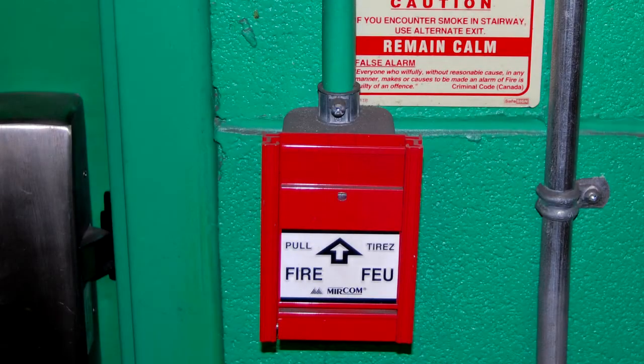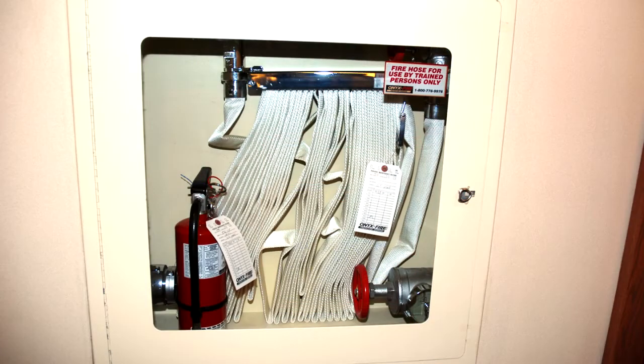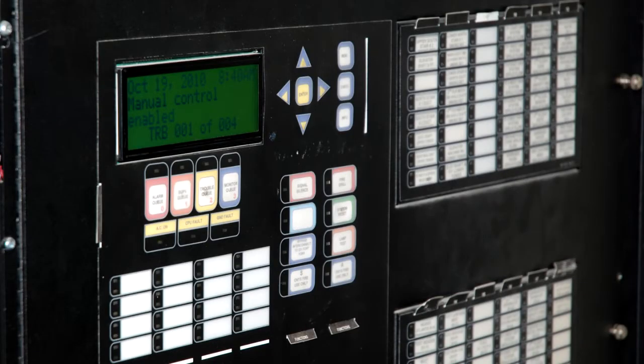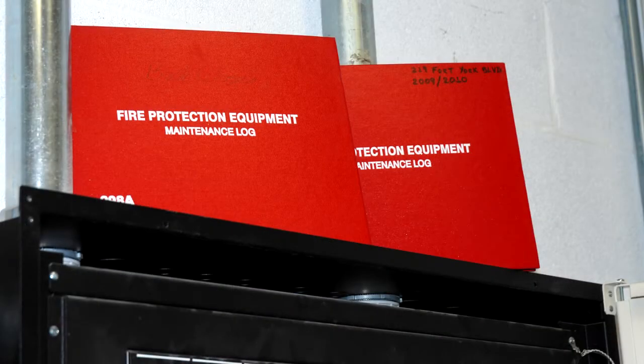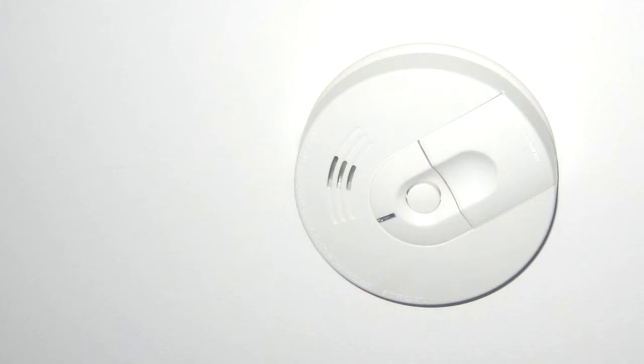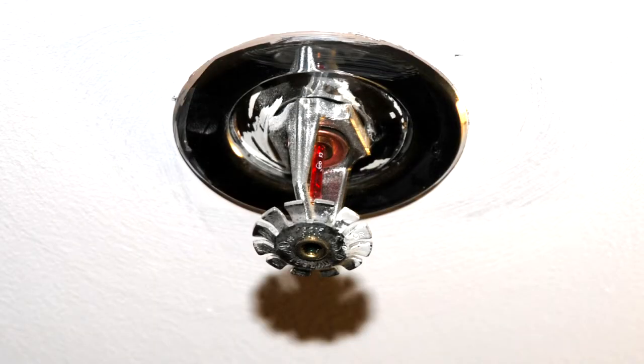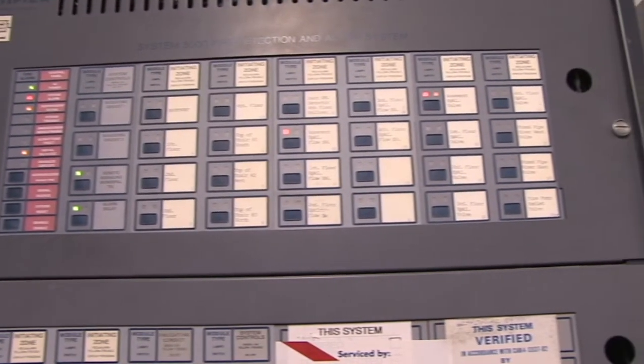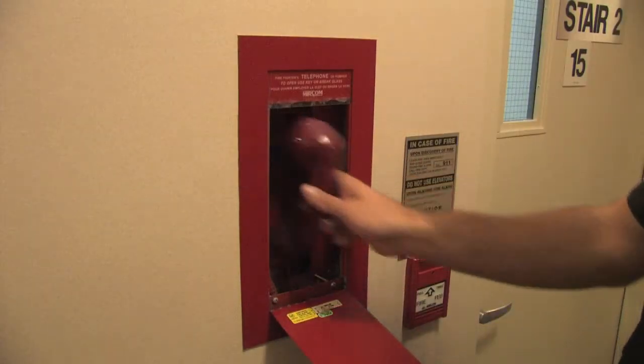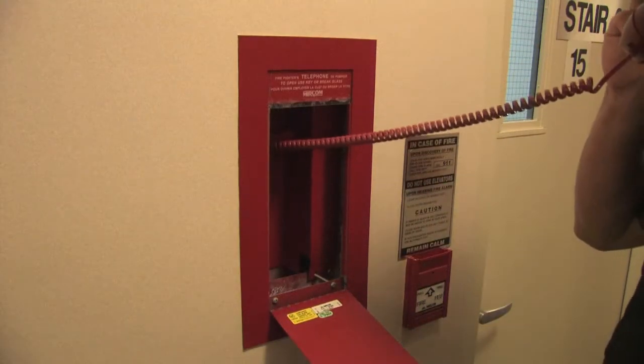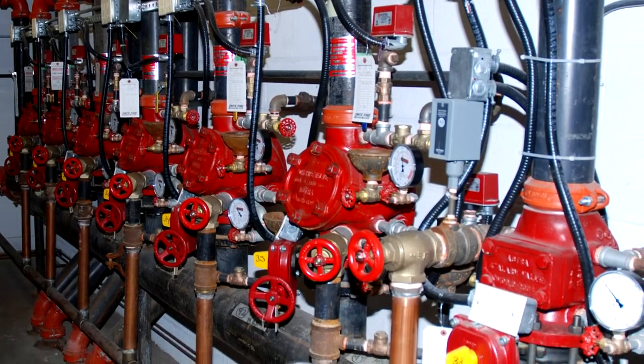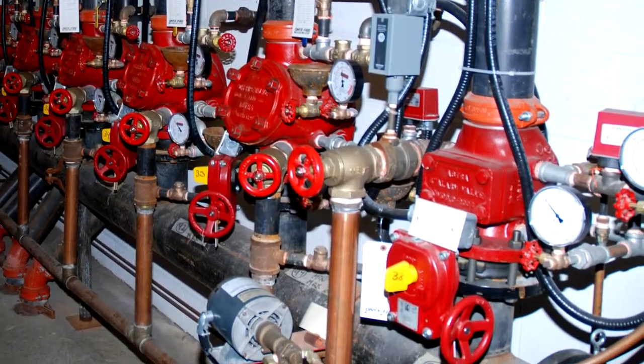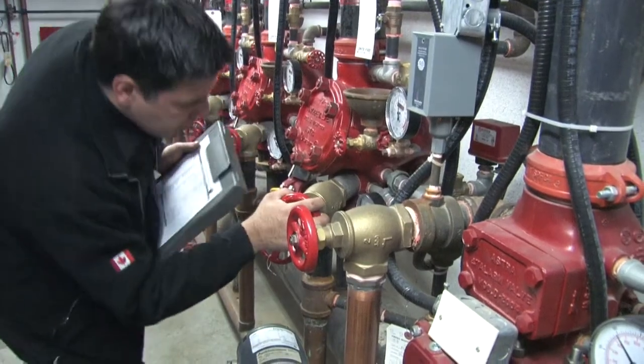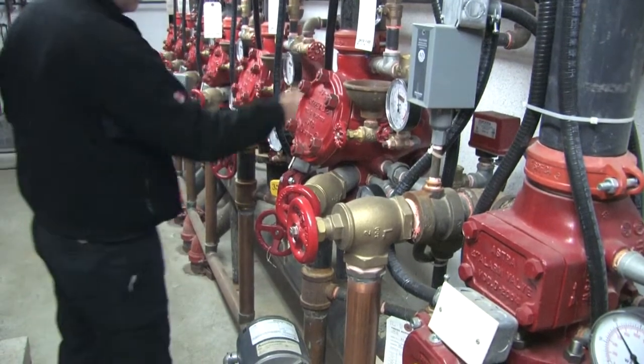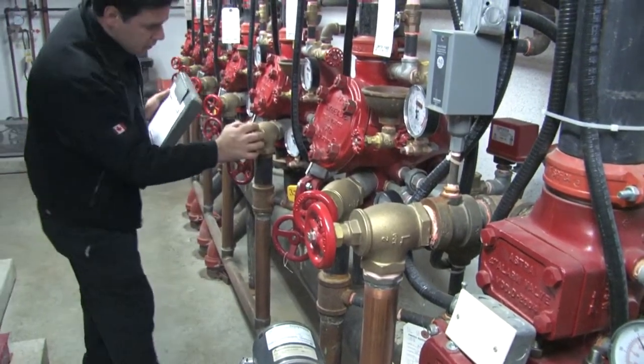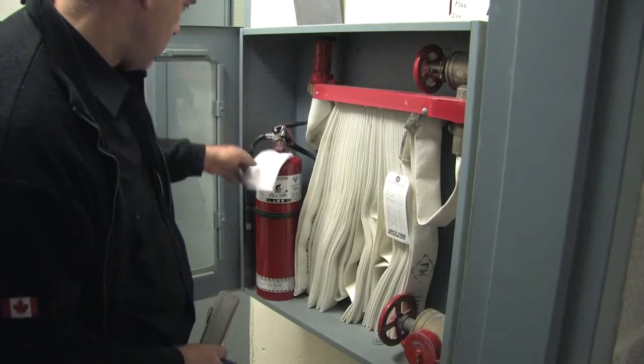The equipment that collectively forms the fire safety system in your building is one of the most crucial building systems you have. It protects not only the people that live in your building, but also the building itself. In this video, we will examine the basic components of a multi-residential building's fire safety system and review the ongoing maintenance necessary to comply with legislation and ensure a safe environment. Your building's life safety components must function when they are needed and therefore must be inspected and tested on a prescribed basis.